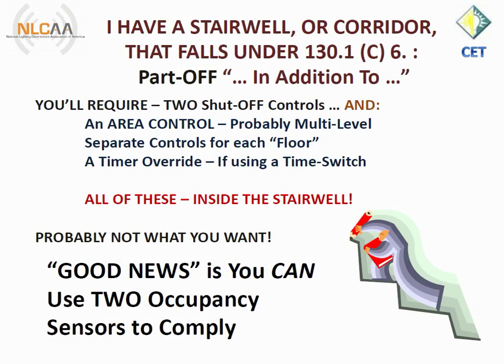You might want to do that. For instance, slightly before and after working hours, you would have an automatic time switch turn on the lower tier of lighting in stairwells and corridors, and then when anybody enters the stairwell or corridor, the rest of the lighting comes on. A little hint, you're going to want to leave that automatic occupancy sensing system running 24/7, because if somebody enters one of these areas and the timer has shut off the lower tier of illumination, then it'll be unsafe if you don't have some lighting coming auto on.